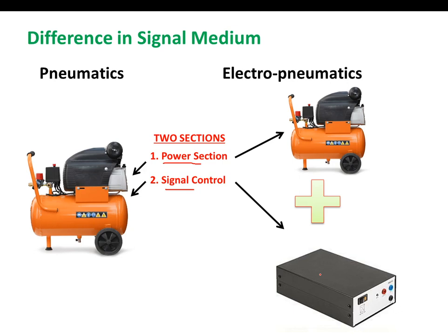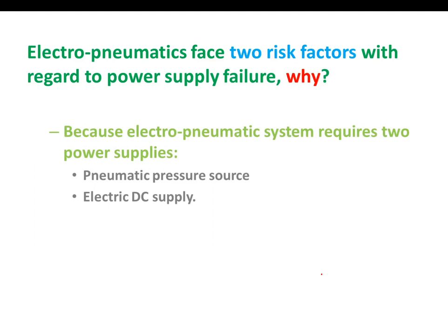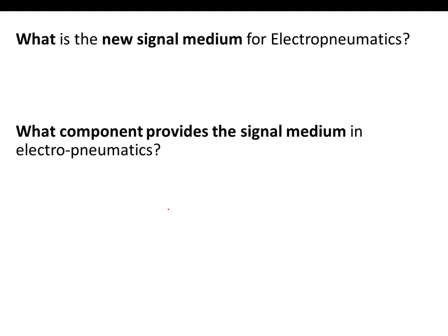Electro-pneumatics faces two risk factors with regard to power supply failure. We now have two power supplies: pneumatic pressure represented by the compressor, and the electric DC supply. So we have one risk factor from pneumatic pressure failure, and the second risk factor is in the case of failure of the DC power supply. The new signal medium in electro-pneumatics is electric current, and the DC power supply provides that signal.